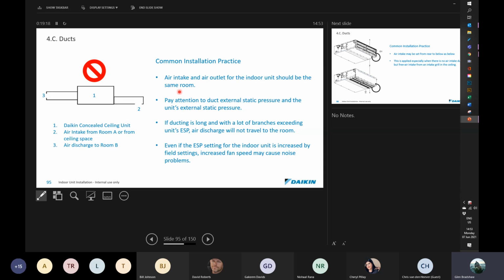And particularly remember that when using flexible ducting, you lose a lot of static pressure. So try and keep those as straight as possible. Pull the kinks out of them, pull them as straight and as few bends as possible when you're using it. And in actual fact, you should only really be using about 1.2 to 1.5 meters of ducting from the main sheet metal duct onto any air register, diffuser.